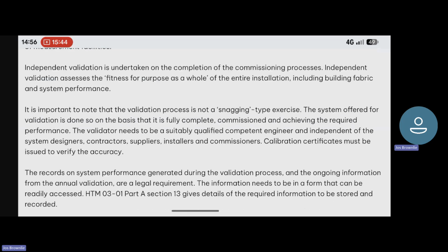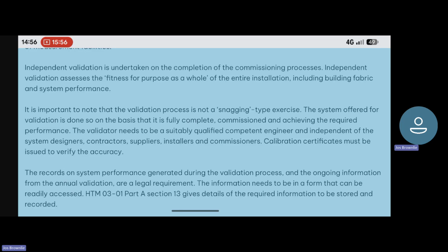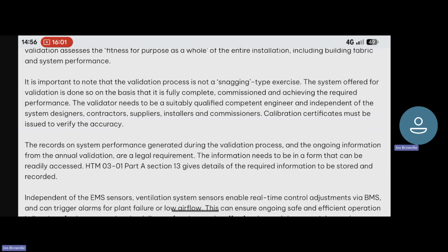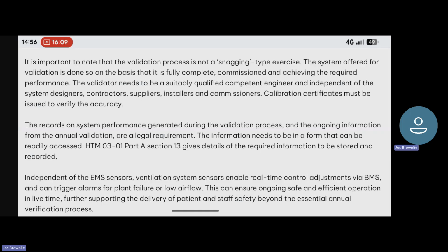Independent validation is undertaken on the completion of the commissioning process. Independent validation assesses the fitness for purpose as a whole of the entire installation, including building fabric and system performance. It is important to note that the validation process is not a snagging type exercise. The system offered for validation is done so on the basis that it is fully complete, commissioned, and achieving the required performance. The validator needs to be a suitably qualified, competent engineer and independent of the system designers, contractors, suppliers, installers, and commissioners. Calibration certificates must be issued to verify the accuracy.